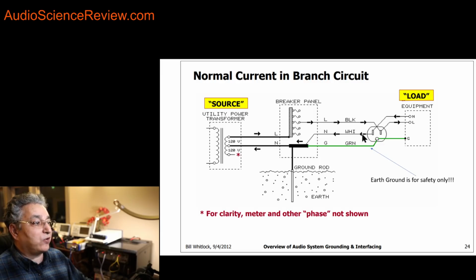But it plays no role in what I just explained. The only current that flows right now is between line and neutral. The ground wire is sitting there doing absolutely nothing. It's basically a redundant path to the neutral wire because they both go to the same place — neutral goes in here, ground goes in here. Remember, this ground path did nothing for you right now because all it's done is connect to a chassis of your equipment doing nothing.